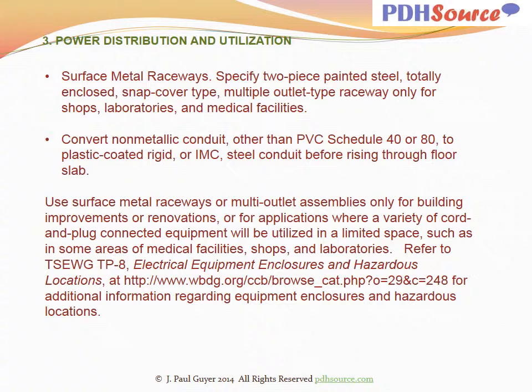Use surface metal raceways or multi-outlet assemblies only for building improvements or renovations, or for applications where a variety of cord and plug connected equipment will be utilized in a limited space, such as in some areas of medical facilities, shops, and laboratories. Refer to TSEWG TP8, electrical equipment enclosures and hazardous locations, for additional information regarding equipment enclosures and hazardous locations.